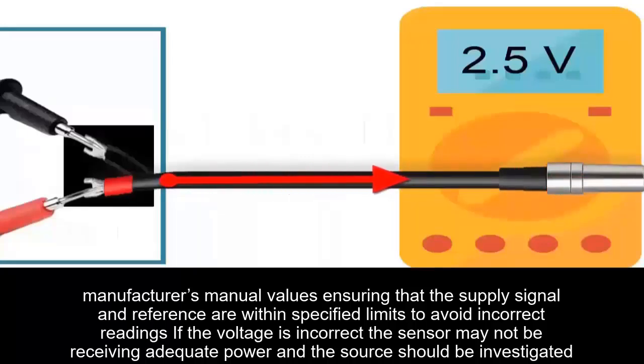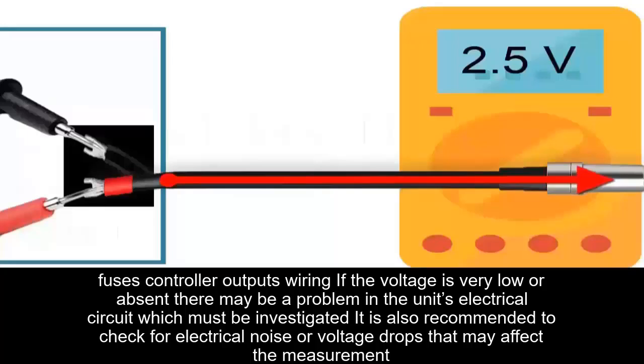If the voltage is incorrect, the sensor may not be receiving adequate power, and the source should be investigated: fuses, controller outputs, or wiring. If the voltage is very low or absent, there may be a problem in the unit's electrical circuit, which must be investigated. It is also recommended to check for electrical noise or voltage drops that may affect the measurement.